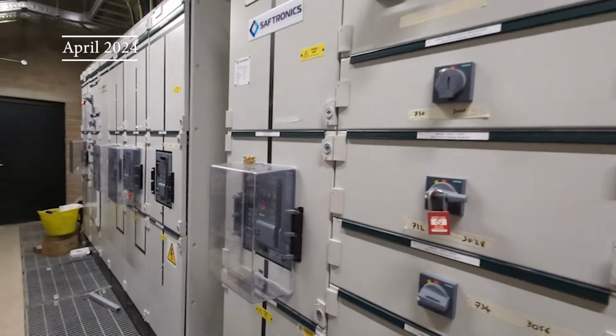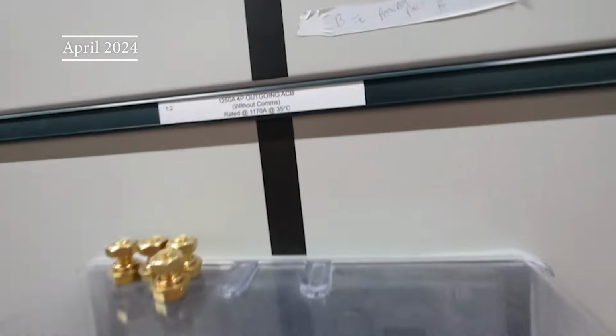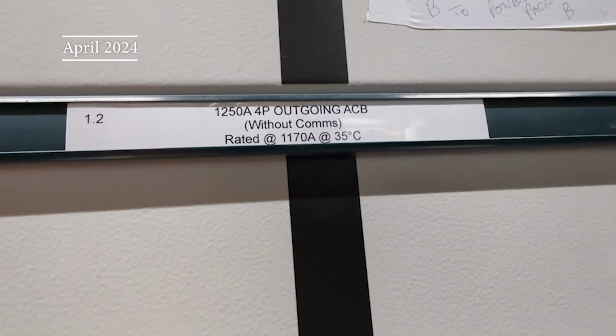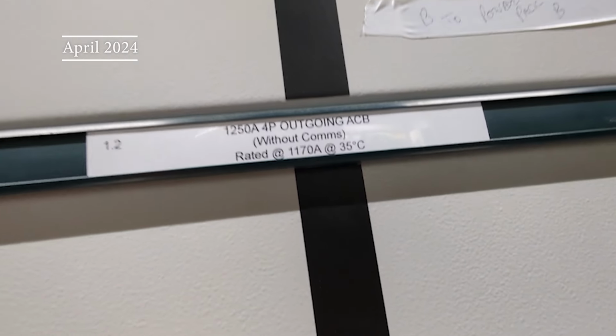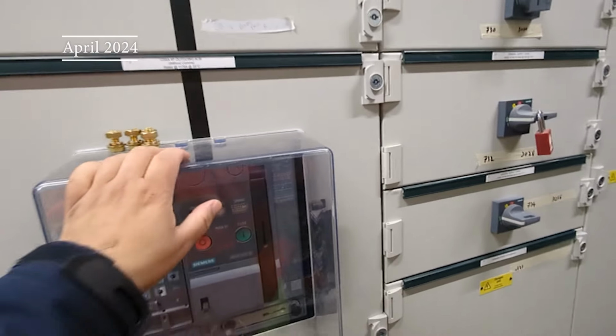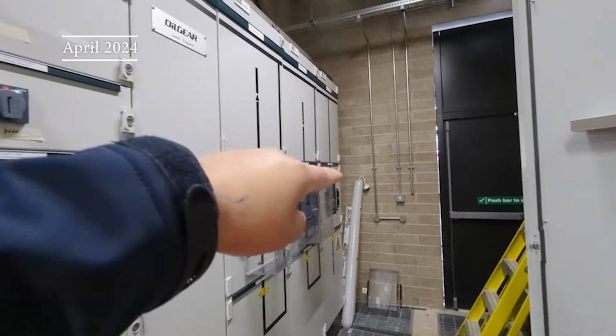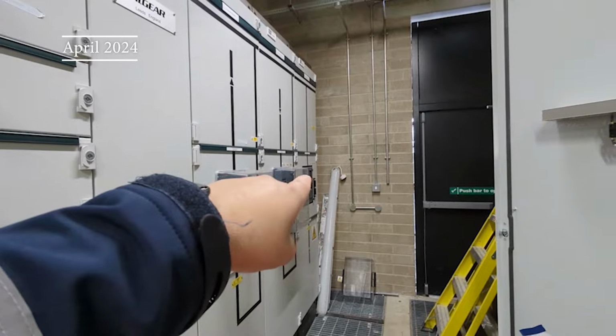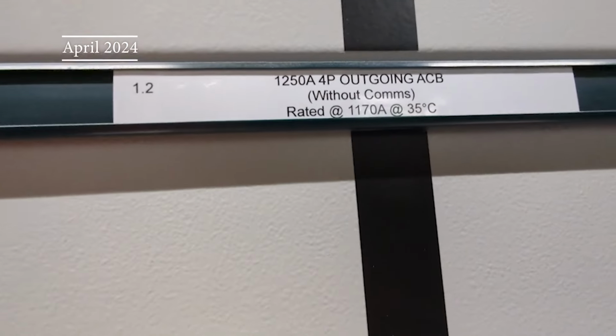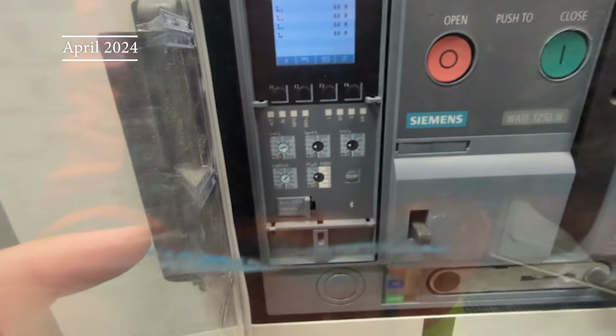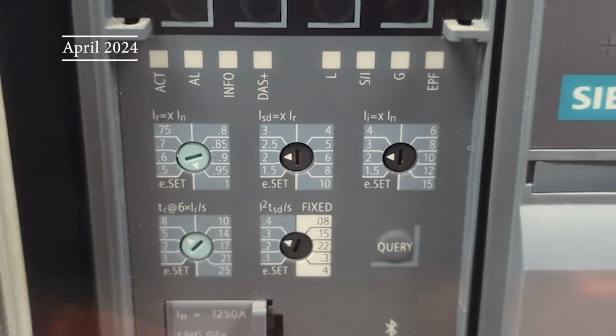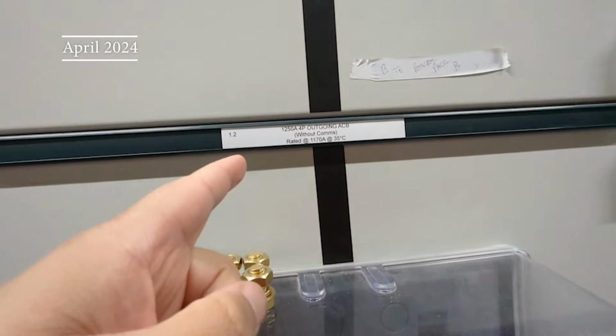The hydraulics are fed from this circuit breaker here, which is a 1250 amp 4-pole circuit breaker, ACB. So this ACB is rated lower than that ACB. That ACB should be blowing at 1500 amps, and it's not blowing. This one's 1250 rated, and I've got it set at 0.95, if you can see that. Yeah, 0.95, so that's even lower. That's like 1100 amps, and this one isn't blowing. This then feeds into the hydraulics.